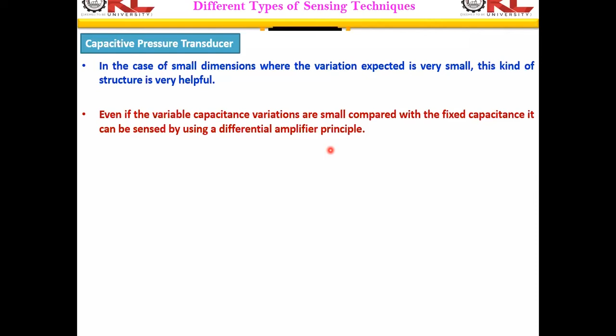temperature independent and have better sensitivity. The change in capacitance relative to the fixed capacitance may be improved, however the capacitance variation is not linear here. When the displacement between the capacitance plates increases, non-linearity arises. That is the drawback. Moreover, fabrication of a parallel plate capacitor on the silicon membrane requires complex fabrication processes. So keeping in view some of these drawbacks, the capacitive sensing principle is not highly suggestible for this particular pressure sensor.